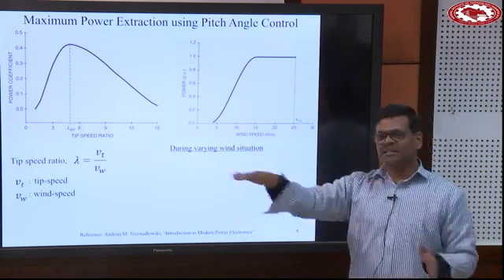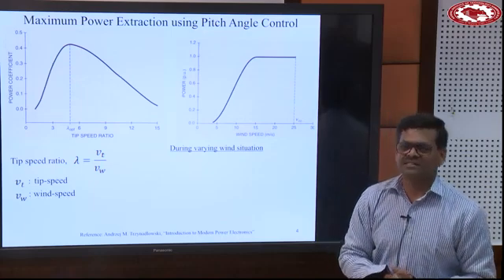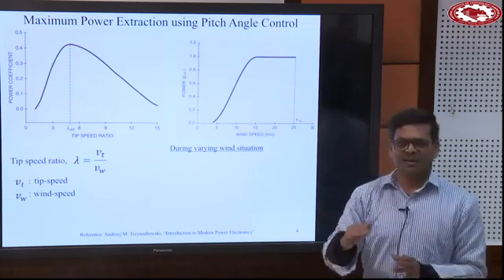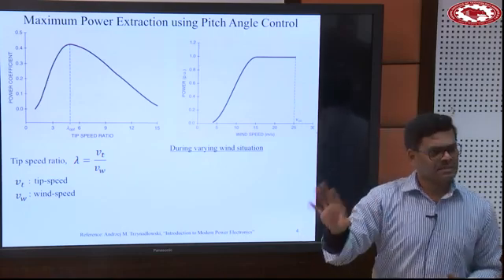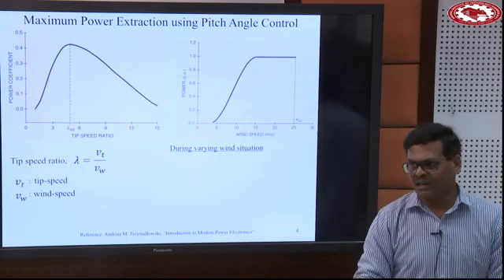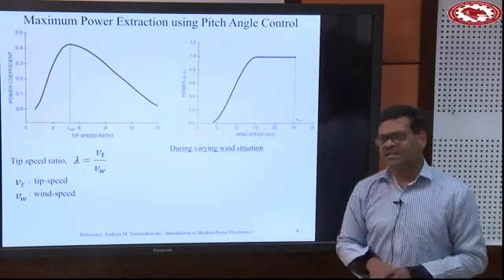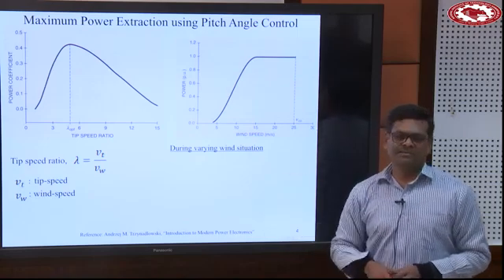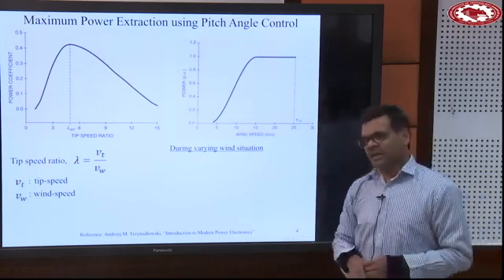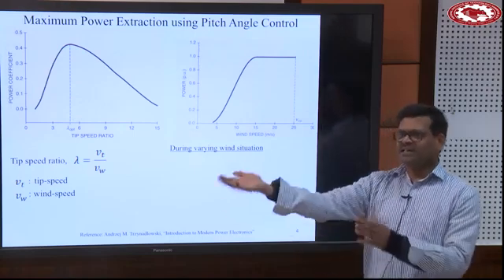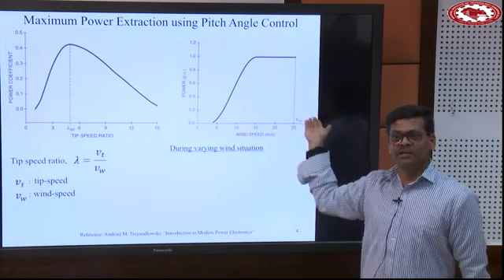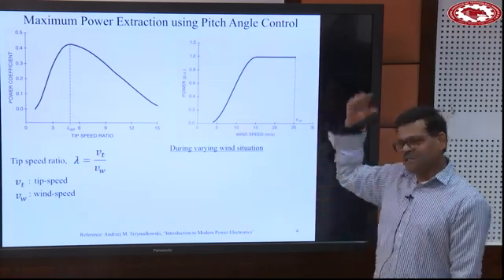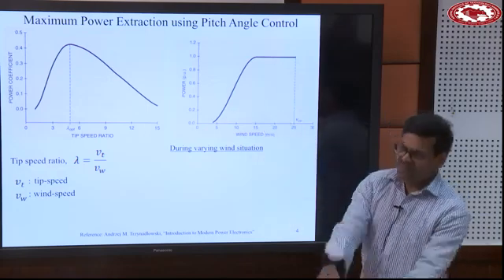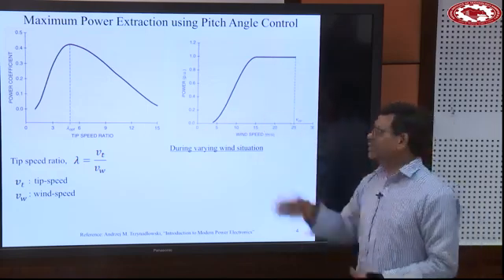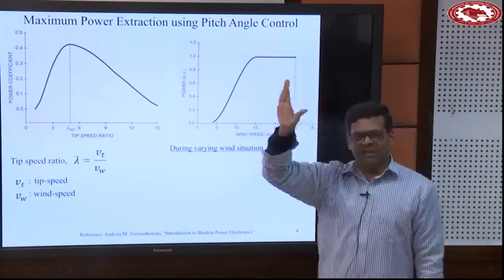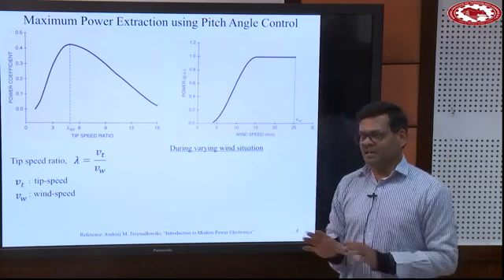Most of the time, whenever we have an electrical system or any other system also, if it is operated very close to full load, the efficiency is maximum. But if it is operated at a lesser loaded situation, then efficiency comes down. Most of the time, the speed is such that it corresponds to 100 kVA. So we have installed the generator. But sometimes the speed is very high. Instead of 12 meter per second, it's going to 15, 18 meter per second, which is capable of leading to higher power. But we have already put up a generator. We cannot change the generator. So therefore, at that time we will have to adjust the turbine blade such that we will get only 100 kVA.